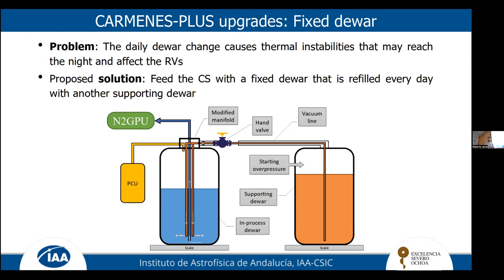what we call the fixed dewar, that is one bottle that is always feeding with liquid nitrogen. And when the fuel, or the liquid level, is too low, we refill the same bottle with a secondary one that is here in orange. Every morning we put this second bottle, full of liquid nitrogen, towards the other one, open the valve, and basically refill the other one. So there's always a flow to the system of liquid nitrogen.